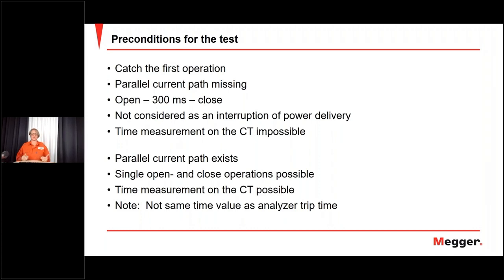And there are different situations. Sometimes you have a parallel path, sometimes you don't. And if you haven't got a parallel path, you will do open close, multiple operation with a delay in between. And this short outage is normally not considered as an interruption of power supply to the delivery to the network. And by this, you will, of course, get a very short interruption, but you can't measure the timing in a good way. Normally, you can measure, say, first trip, you're measuring the CTs, but when you don't have a parallel path, this is not so interesting information.